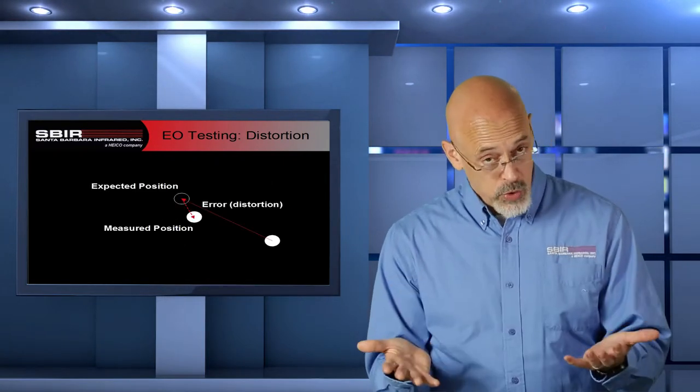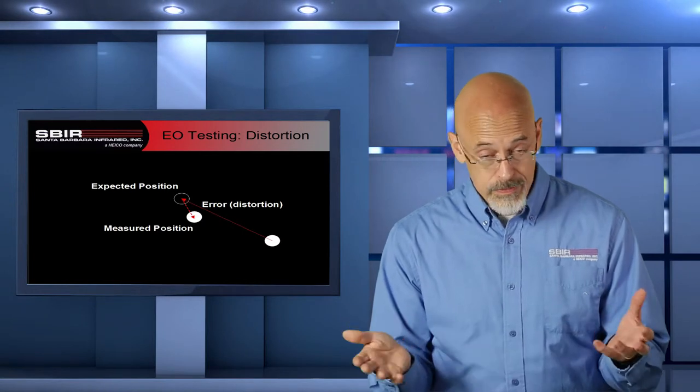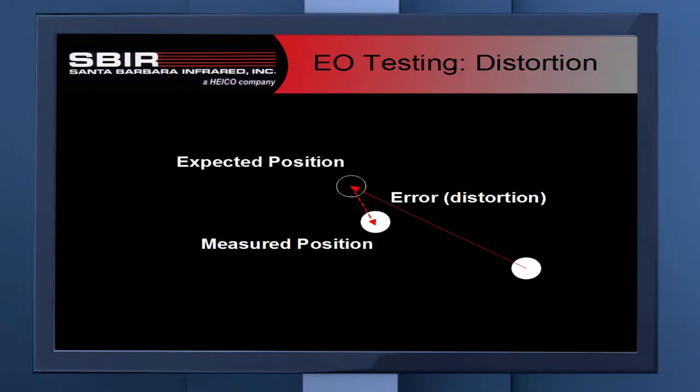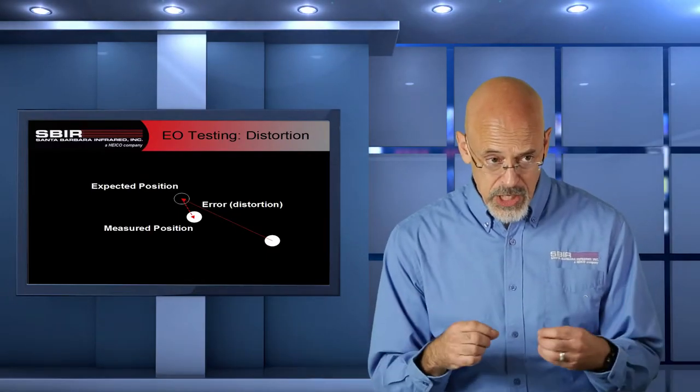We measure this test using our standard boresight measurement for a centroid of every one of those pinholes, and we compare the position that we've measured to where we expect it to be. That offset is the error that we're going to refer to. The error can be divided by the overall field of view to get a percentage.